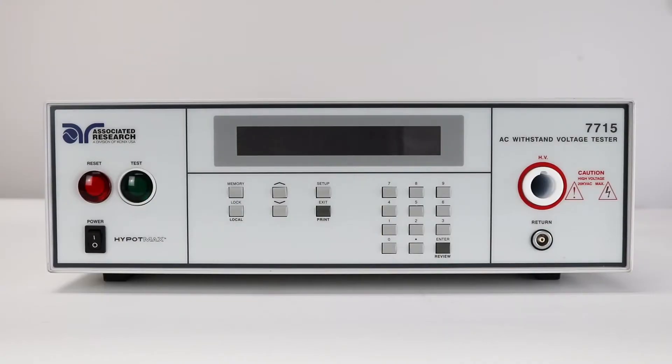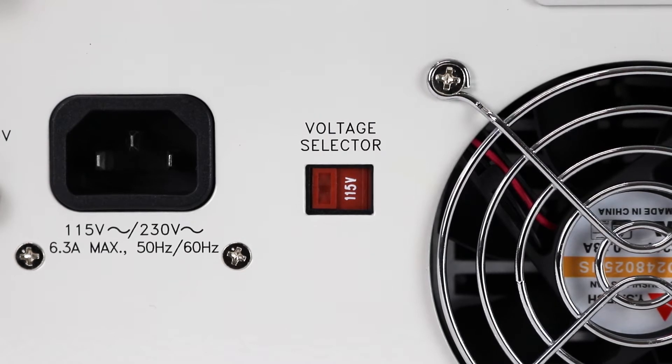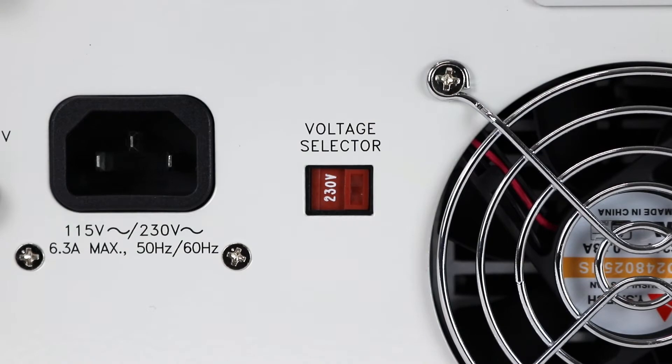First, you'll need to power up your HypotMAX instrument. Check to be sure the correct input line voltage has been selected on the rear panel, either 115 volts AC or 230 volts AC.